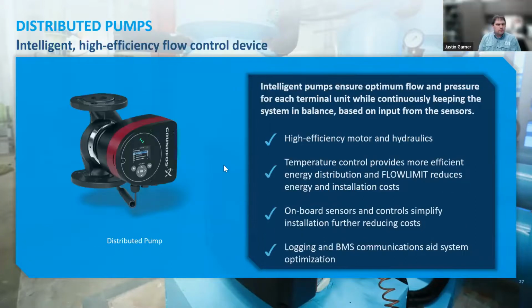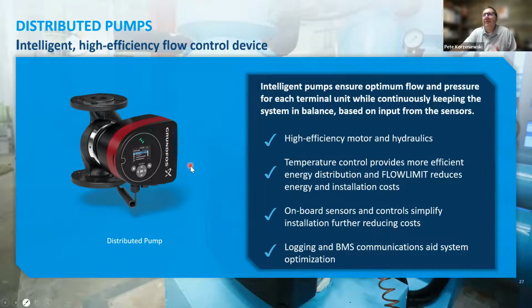On the distributed pumps, we're looking at high efficiency, intelligent pumps, with improved hydraulics to aid in the efficiency gains that we're looking for. We've got temperature control, and I'll talk about how we're going to control these pumps, but we're looking at outgoing air temperature or supply air temperature. That will give us a much better heat transfer and more efficient energy distribution. Depending on how smart your pump is, you'll have some control features that allow you to get rid of other hardware in the near air handler piping. And then onboard sensor controls will help you in the setup.